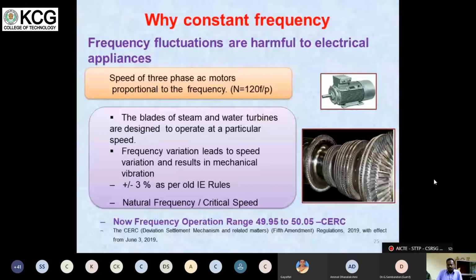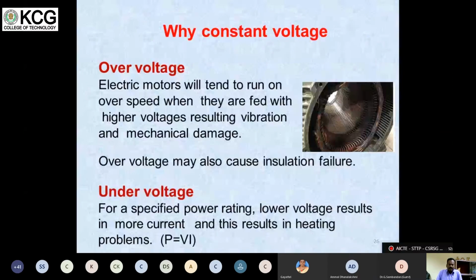Then what is the voltage problem? If there is higher voltage in the system, again we'll have the same problem. Electrical motors will tend to run in overspeed when they are fed with higher voltage, resulting in vibration and mechanical damage. So with higher voltage also we have a problem. Mechanical damage will happen, vibration will happen, and at the same time there is insulation failure in the electrical system, transformer, motor, etc. Under voltage, for the same power, the current drawn by the equipment is more, and it leads to more losses in the system. Simply we have to incur more losses in the transmission and distribution system. So it is not desirable. Over voltage and under voltage are not desirable.